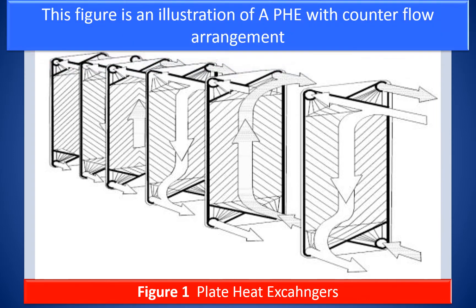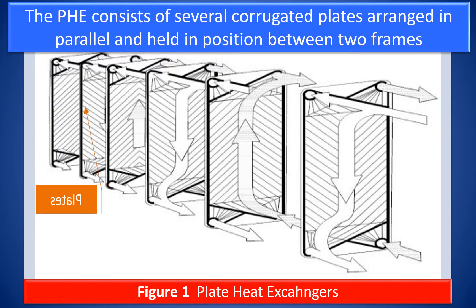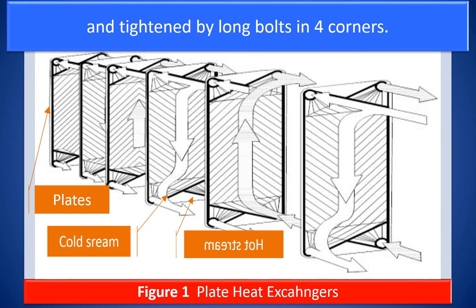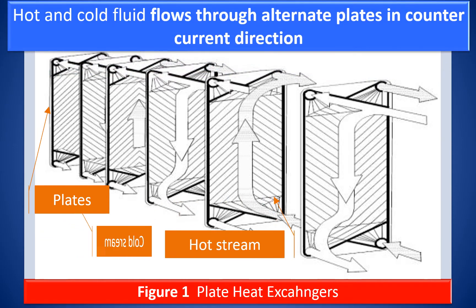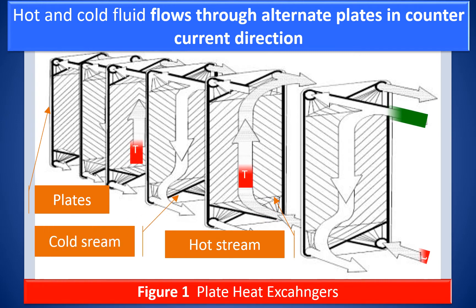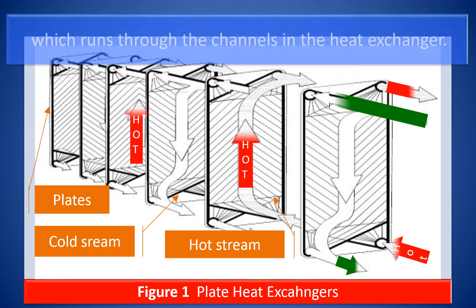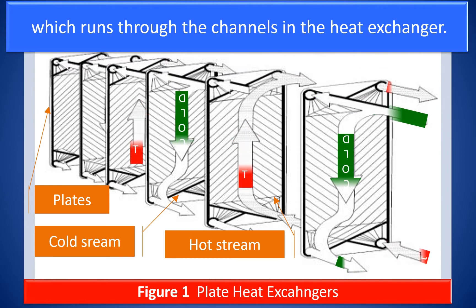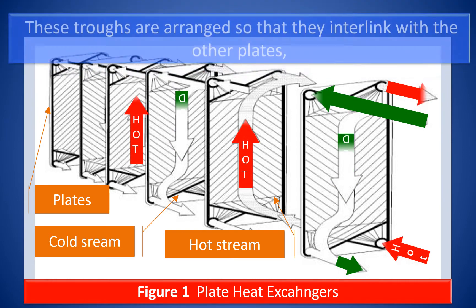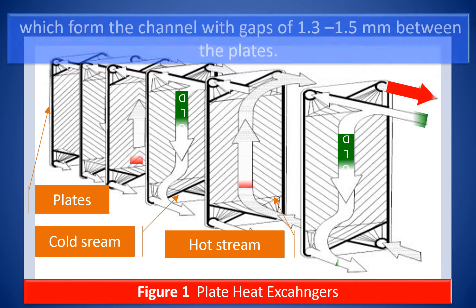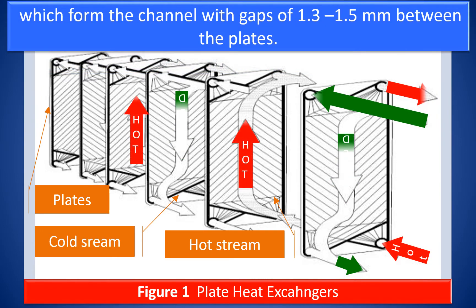This figure illustrates a plate heat exchanger with counter-current flow arrangement. The plate heat exchanger consists of several corrugated plates arranged in parallel and held in position between two frames, tightened by long bolts in four corners. Hot and cold fluid flows through alternate plates in counter-current direction. The plates are pressed to form troughs at right angles to the direction of flow, which runs through the channels, with gaps of 1.3 to 1.5 mm between the plates.